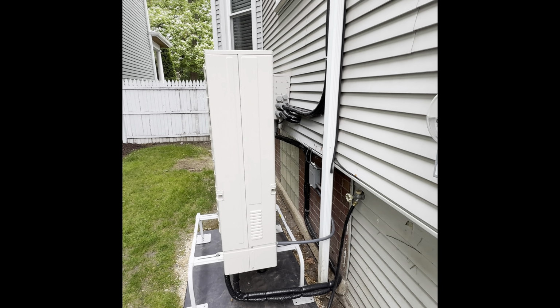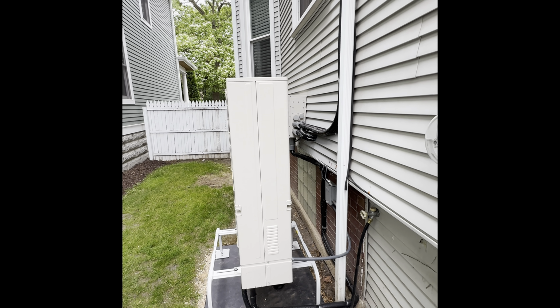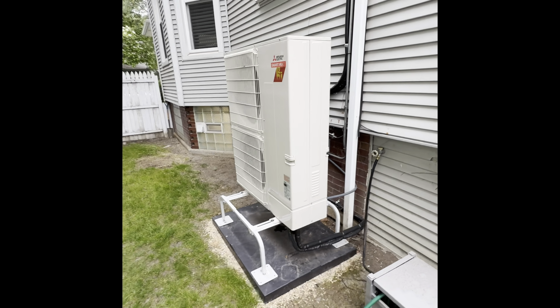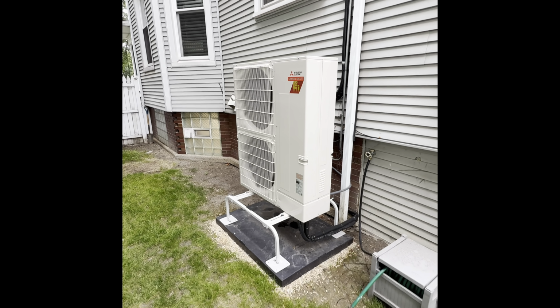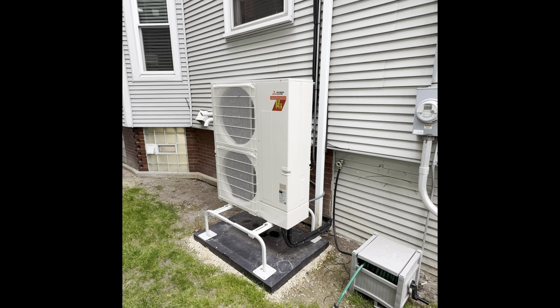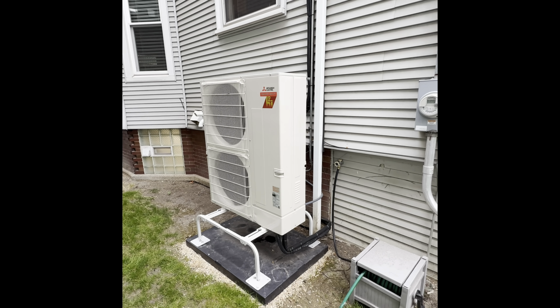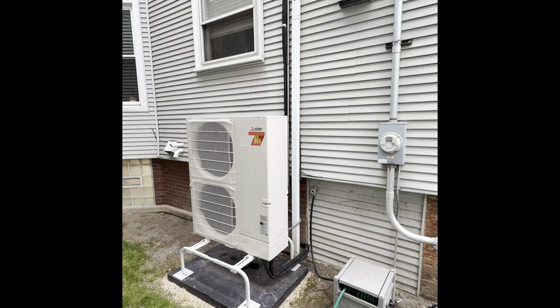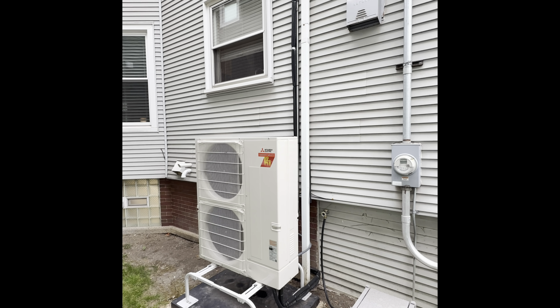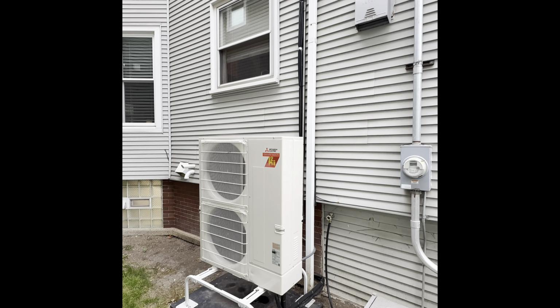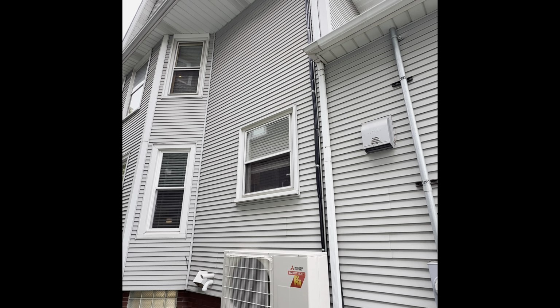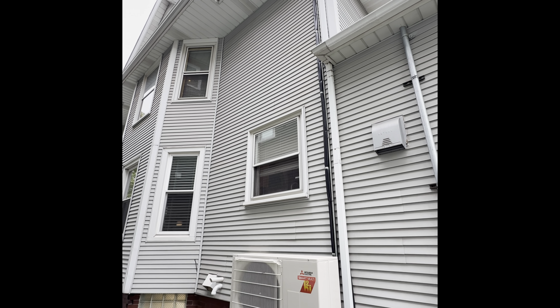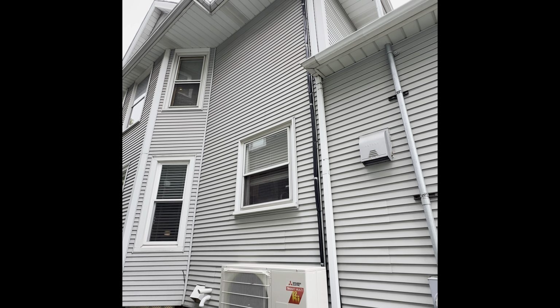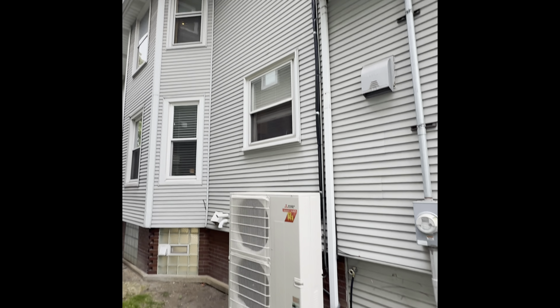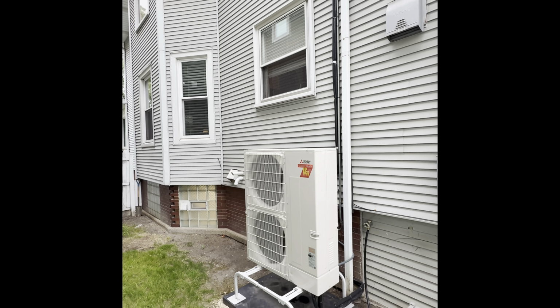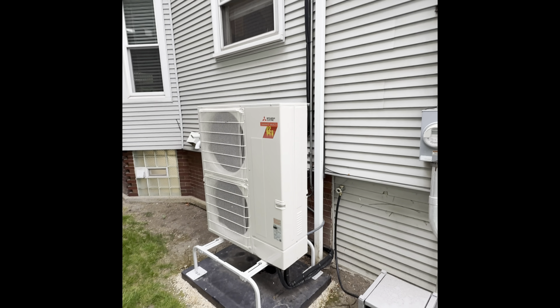And with this setup, we have two zones. This is replacing a split pack system that they used to have. They only had cooling upstairs and a boiler for heating. We actually removed the boiler and most of the radiators. And now the system is going to be taking over for the upstairs zone. The heat pump is going to be doing 100% of the heating. It has electric backup heating if needed. But on the lower level, basement and main level, we do have a gas furnace connected to our heat pump.